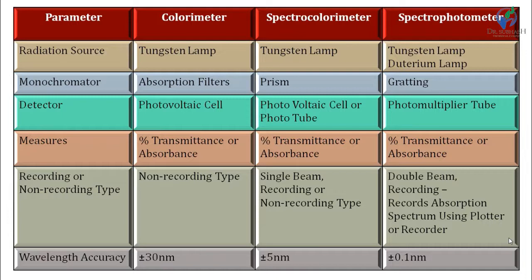All of these instruments measure percentage transmittance or absorbance of a sample. Regarding recording type: recording means we can store results in hard copy or soft copy; non-recording type means we cannot store results — we just read the value from the display. Colorimeters are non-recording type; we just note down the percentage transmittance or absorbance. Spectrocolorimeters may be recording or non-recording, and spectrophotometers can record absorption spectra using a plotter or recorder.